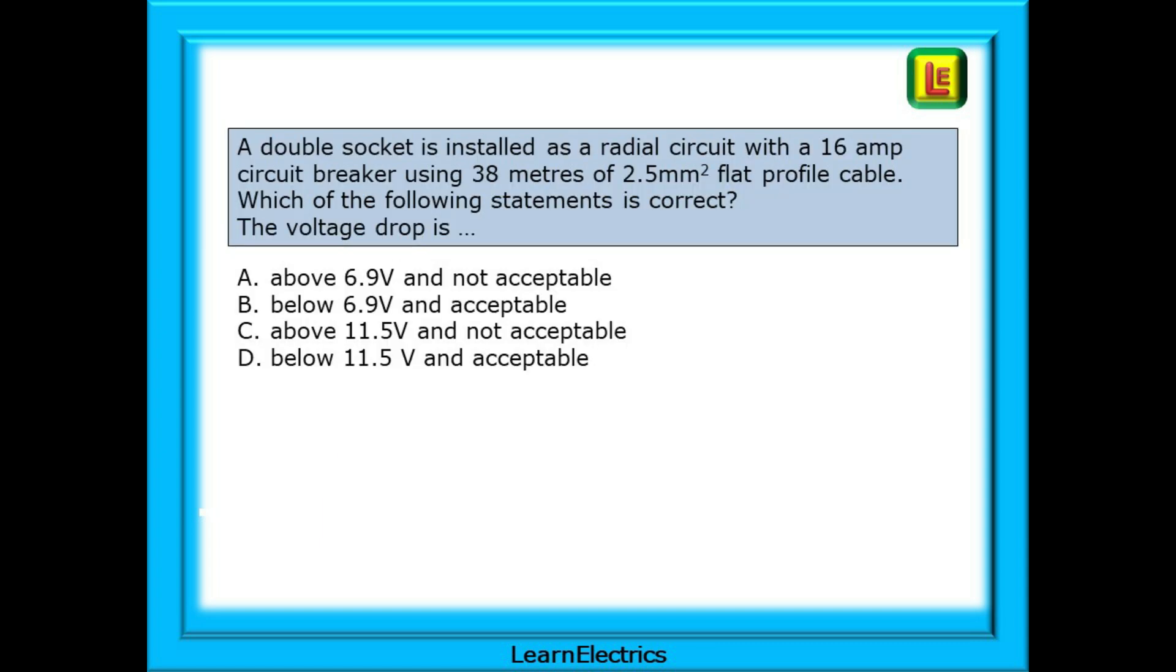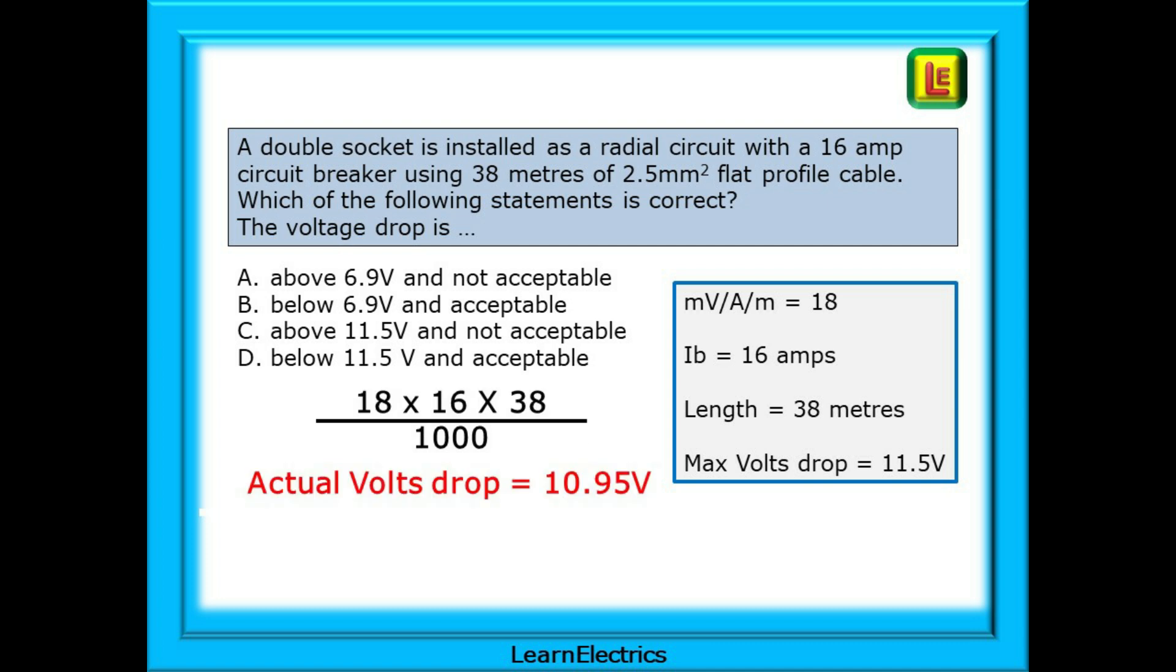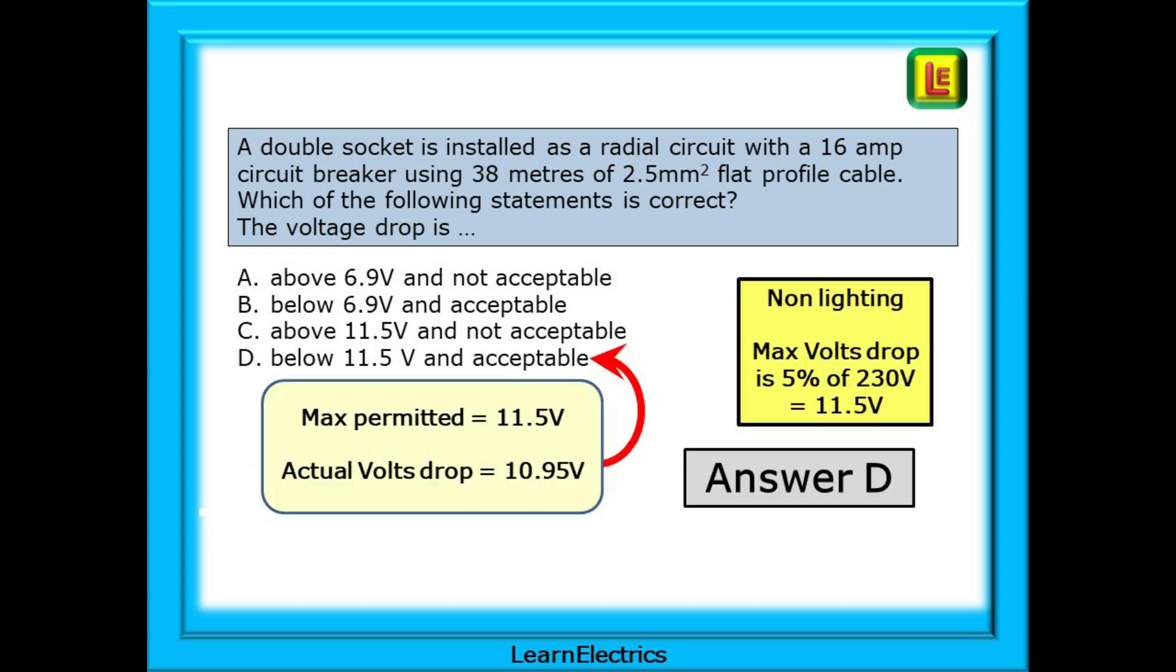Question 3 now. A double socket is installed as a radial circuit with a 16 amp circuit breaker using 38 metres of 2.5 square millimetre flat profile cable. Which of the following statements is correct? And the question asks, the voltage drop is what? And there are 4 possible answers. Only one is most appropriate. Pause the video and attempt the question yourself before seeing the answer. Complete the data box with the numbers you need from the question. Enter the numbers into the equation. Do the calculation and out should come the voltage drop 10.95 volts. Now decide if 10.95 volts is an acceptable voltage drop for a non-lighting circuit and choose your answer. You should choose answer D. The voltage drop is below 11.5 volts and is acceptable.